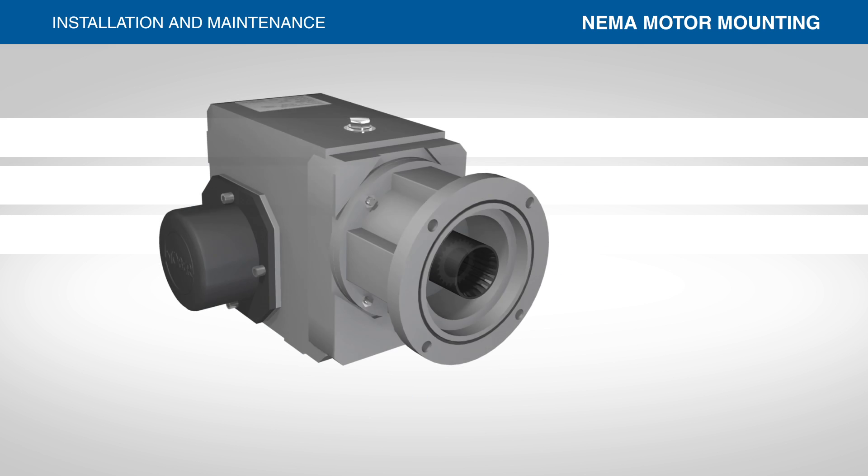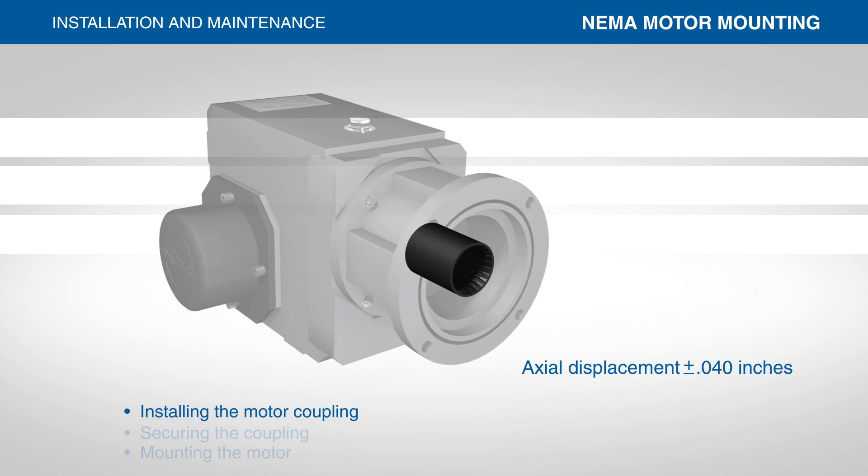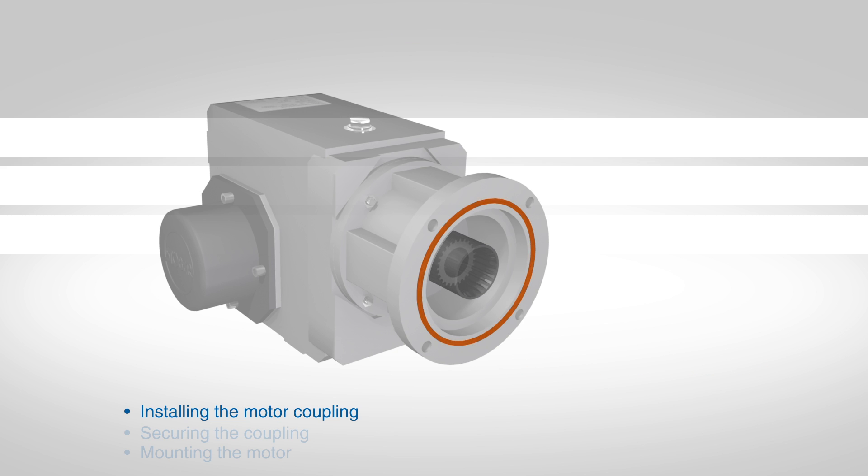Leave the motor coupling sleeve inside the motor adapter. The sleeve should move freely in an axial direction. Make sure the O-ring is seated in the groove of the motor adapter face.